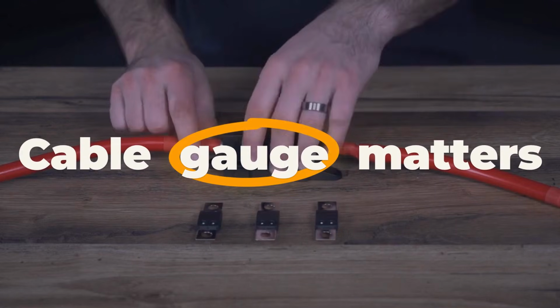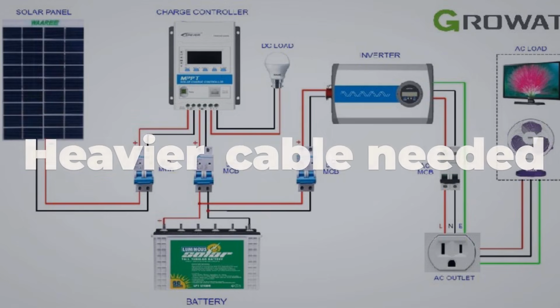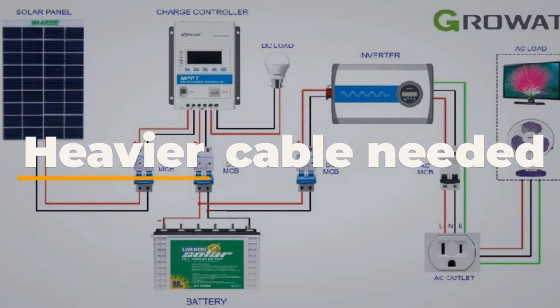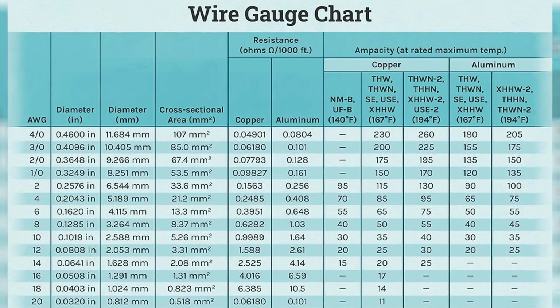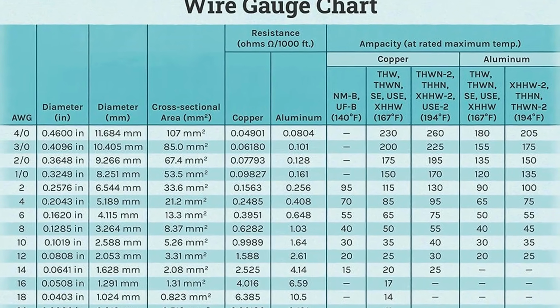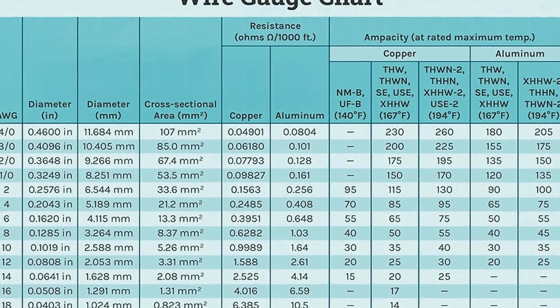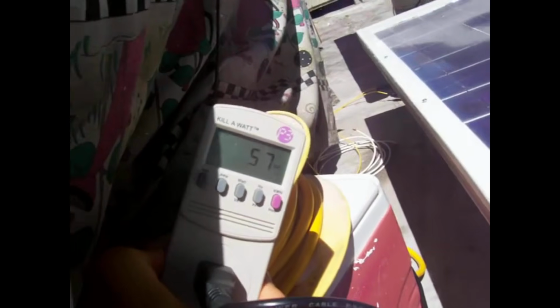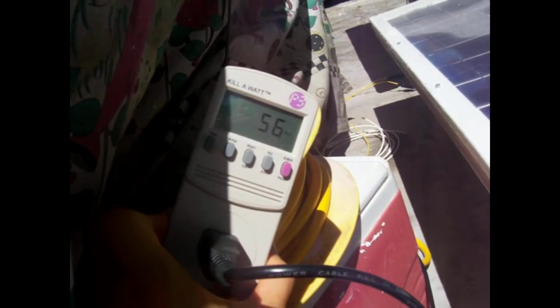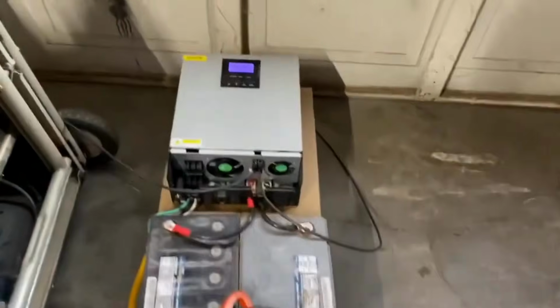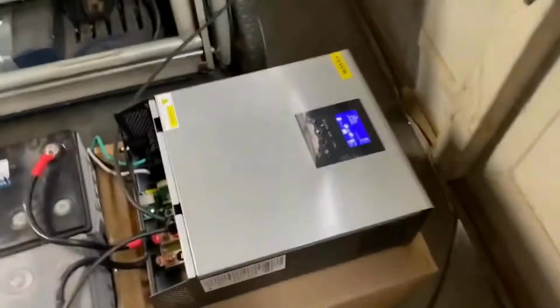Cable gauge matters in a specific direction. The longer the run and the higher the current, the heavier the cable needs to be. Budget kits routinely ship with 10 or 12 gauge wire on inverters rated for loads that demand 6 or 4 gauge. A 2-foot run might survive it. A 6-foot run turns that mismatch into measurable voltage drop and heat at the connection points.